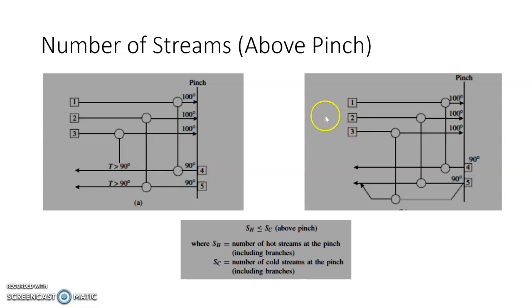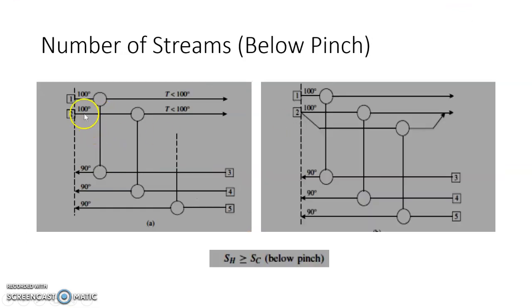Similarly, below the pinch, if we have three cold streams and two hot streams, every cold stream at the pinch requires a corresponding hot stream at the pinch. Otherwise, the temperature difference would fall below delta T minimum. Hence, below pinch we require the number of hot streams to be greater than or equal to the number of cold streams — we split hot streams when the numbers are unequal. We split cold streams above pinch and hot streams below pinch.